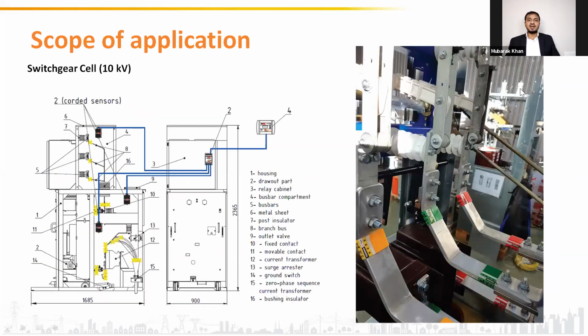In a circuit breaker panel, normally we have an incomer compartment, which is a cable compartment. Then we have a circuit breaker compartment and a bus bar compartment. So we can install the stickers at the cable terminations, circuit breaker jaw connections, as well as the bus bar joints. We can have one sensor in the cable compartment, one sensor in the breaker compartment, and one sensor in the bus bar compartment. Okay. And then all these sensors can be connected to FPA, and FPA can be connected to FPC.